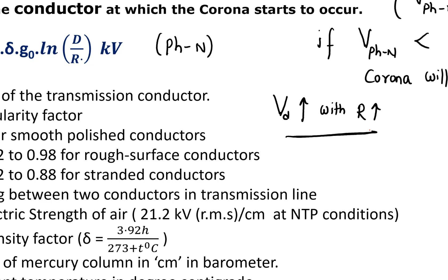So that's why at higher voltages, that means for voltages above 220 kV, we try to intentionally increase the size of conductor so that the corona occurrence probability is reduced. That's why we go for bundled conductors, expanded ACSR conductors and hollow conductors. Mainly we intentionally want to increase the size of conductor so that the corona is reduced. Okay.